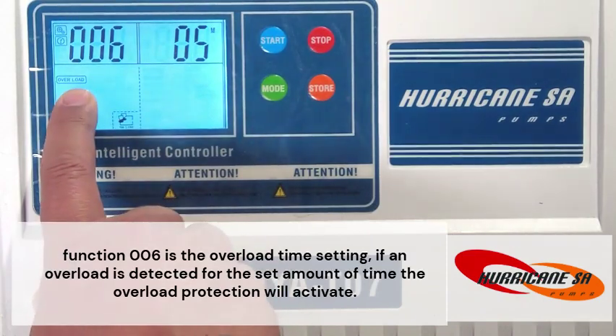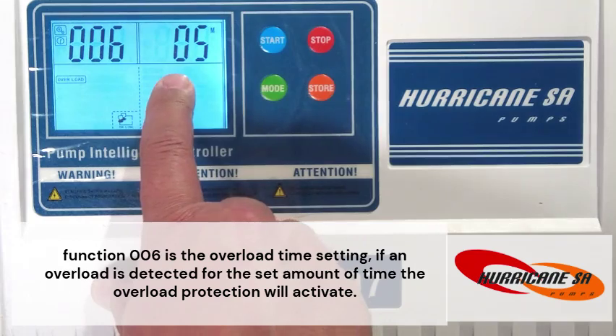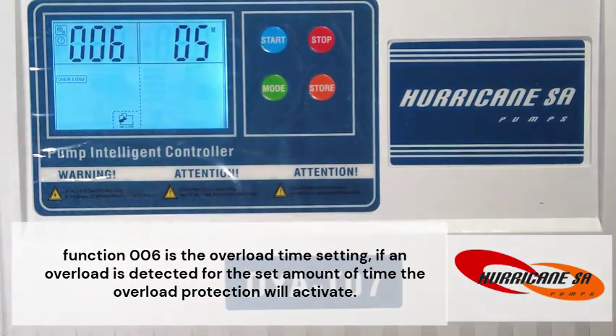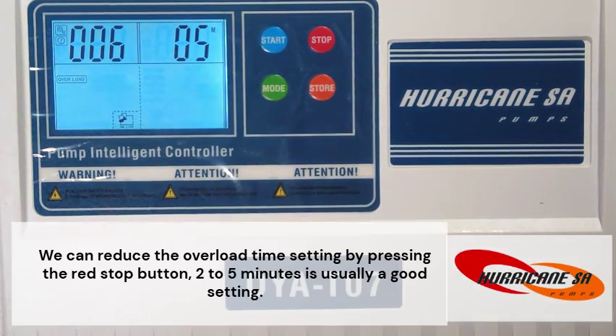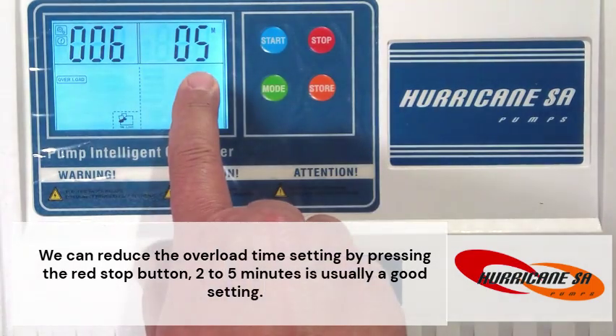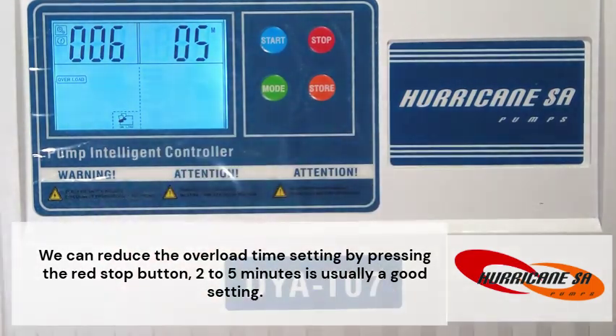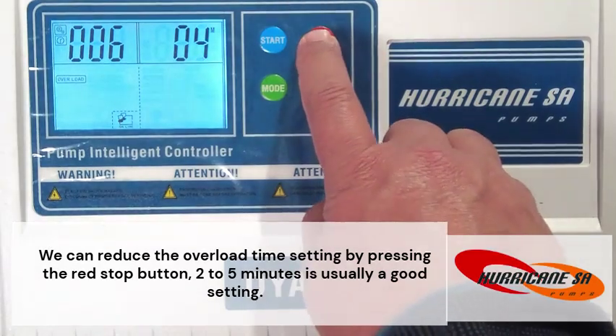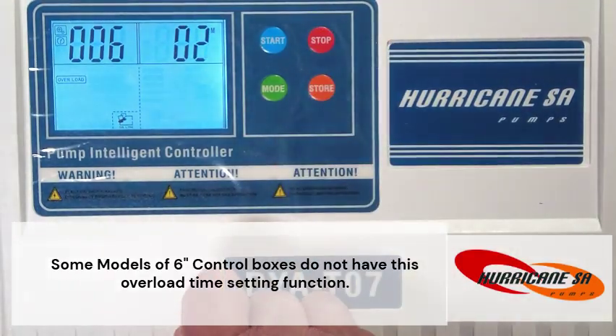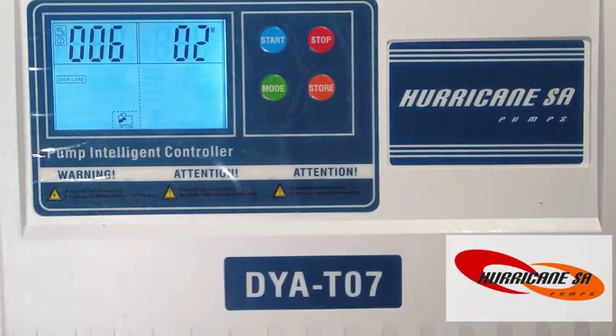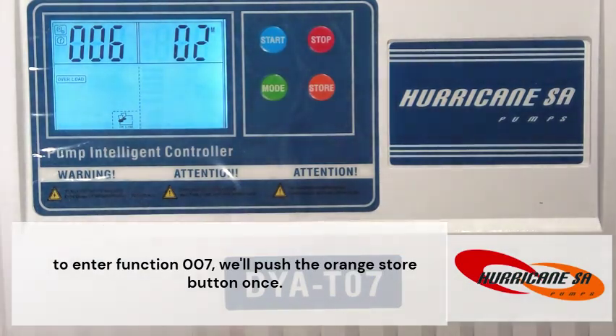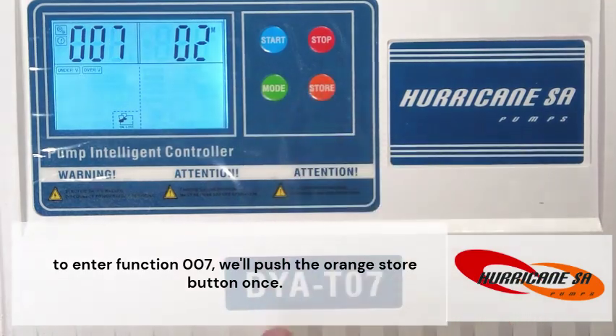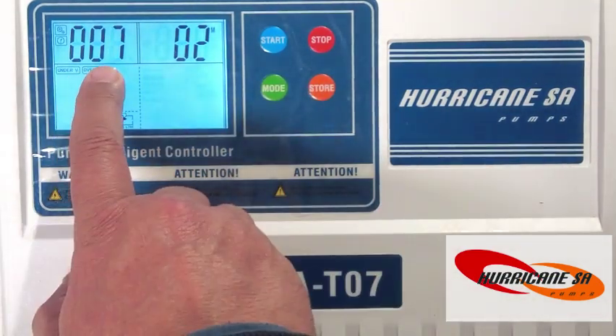Function 006 is the overload time setting. If an overload is detected for the set amount of time, the overload protection will activate. We can reduce the overload time setting by pressing the red stop button. 2 to 5 minutes is usually a good setting. Some models of 6-inch control boxes do not have this overload time setting function. To enter function 007, we'll push the orange store button once.